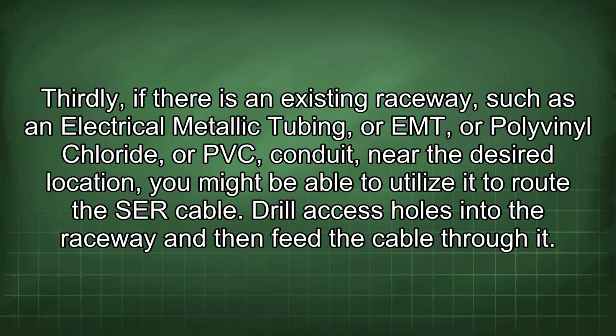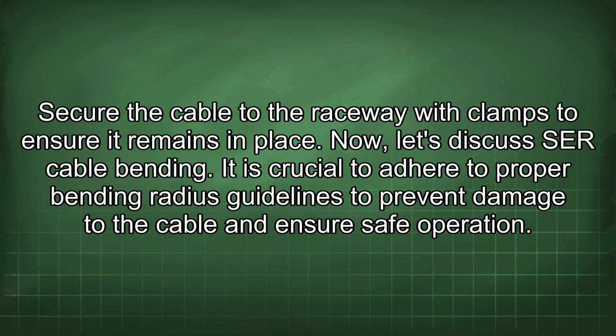Thirdly, if there is an existing raceway, such as an electrical metallic tubing or EMT, or polyvinyl chloride, or PVC conduit near the desired location, you might be able to utilize it to route the SER cable. Drill access holes into the raceway and then feed the cable through it. Secure the cable to the raceway with clamps to ensure it remains in place.